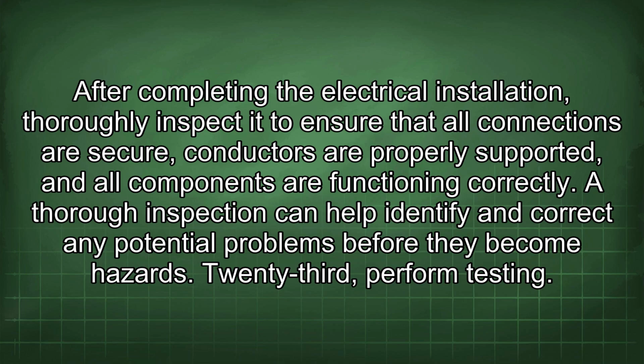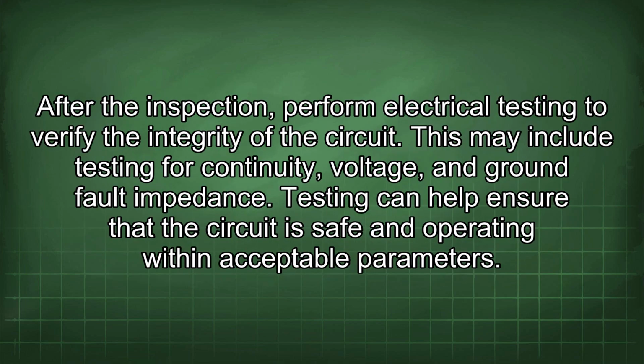23rd, perform testing. After the inspection, perform electrical testing to verify the integrity of the circuit. This may include testing for continuity, voltage, and ground fault impedance. Testing can help ensure that the circuit is safe and operating within acceptable parameters.